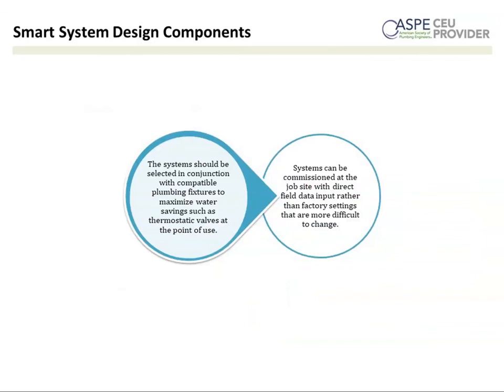So again, systems should be selected in conjunction with compatible plumbing fixtures to maximize water savings, such as thermostatic valves at the point of use. The question sometimes comes up, around conservation, how would a thermostatic valve at a point of use apply to this? Essentially, because it is trying to maintain a set point, it's going to only require hot water when needed. The internal mechanism is going to make an adjustment, and when hot water is only needed to increase the set point, or if there's too much hot water, it's going to increase the cold water. So it's a small device that's precisely regulating the amount of hot water that's coming into the valve and to the fixture.